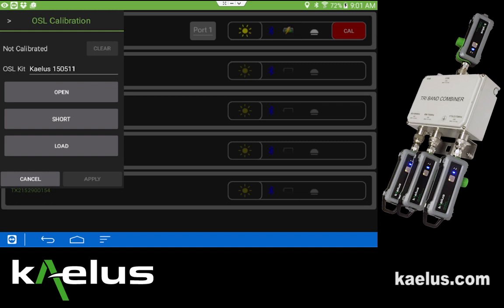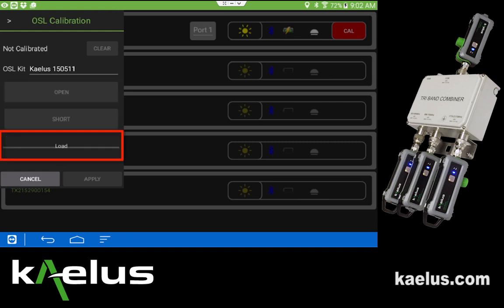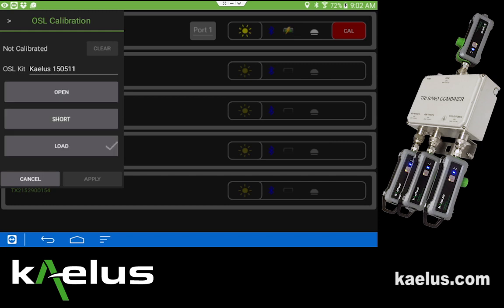The calibration methodology for the Kaelus iVA does not require that the cal standards be connected in any specific order. In this particular case, I've connected the load and we'll measure it first. As the load data is measured, it is done so at every possible IVA frequency. This means there's no need for additional calibrations after the initial cal. Smaller band cals do not improve the calibration applied to the IVA.